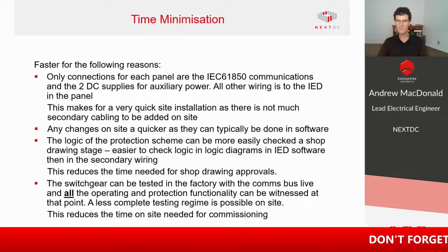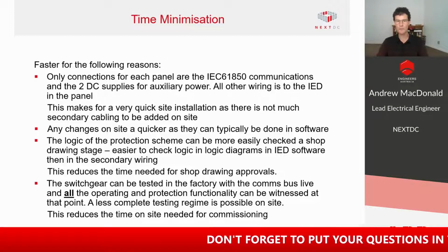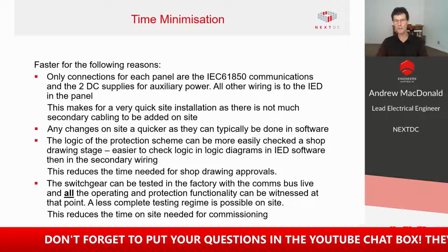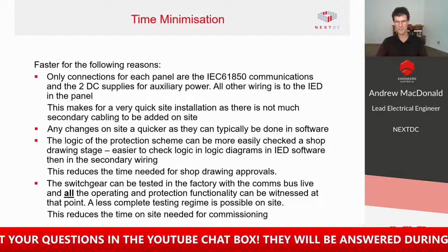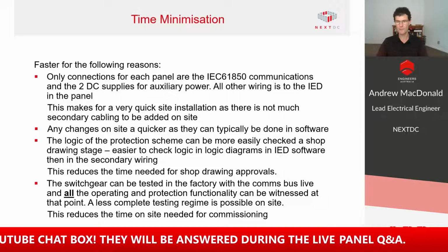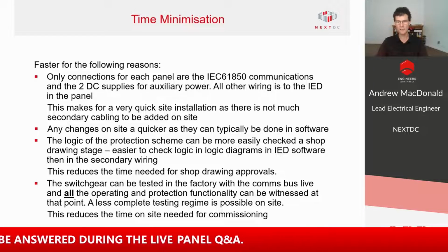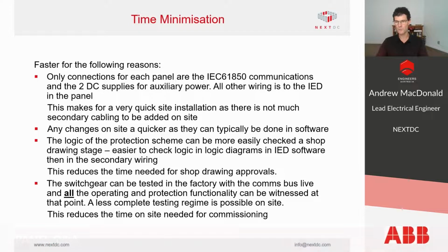Time minimisation. We have a design, we want to get our facilities up and running as quickly as possible, and our perception is that it would be faster to use the digital switchgear for the following reasons. The only connections we have between our panels are the IEC 61850 communications links on optic fibre, which is pre-terminated, and the two DC supplies for the auxiliary power. All other wiring within the panel is to the IED and done as part of the factory work.